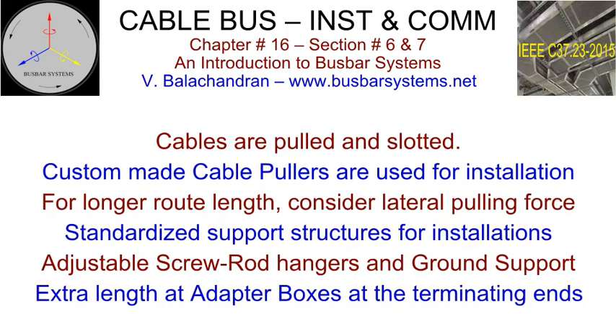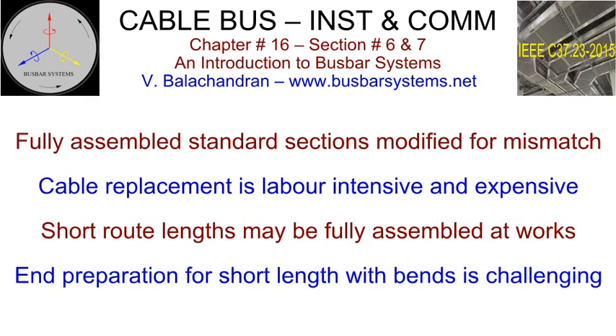Standardized support structures for specific ratings of cable bus are manufactured for ease of clamping for indoor and outdoor installations. Adjustable screw rod hangers for indoor support from the ceiling and adjustable ground support are provided by the manufacturers for ease of installation. An extra length of cable is provided at both ends for negotiating the cable inside the adapter boxes at the terminating ends. Depending upon route lengths, fully assembled standard sections comprising an enclosure, support blocks, clamps, earth bus, etc. are dispatched to the site to cater to the requirement of a mismatch. Depending upon the requirements of the mismatch, a makeup piece can be attached to the existing arrangement for an accurate connection. The makeup piece can be cut from a standard section, supplied as spare for this very purpose, and drilled to suit the site conditions.